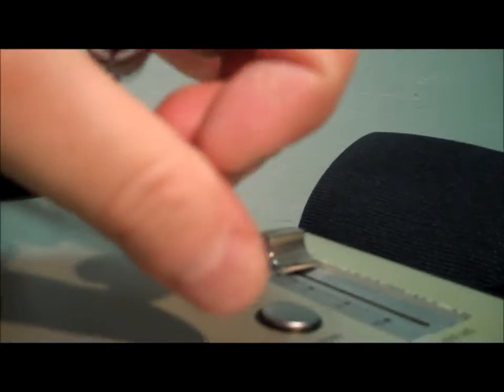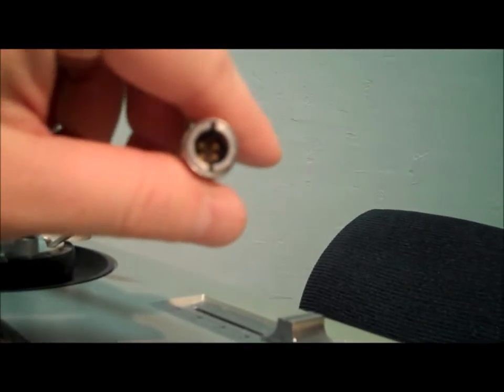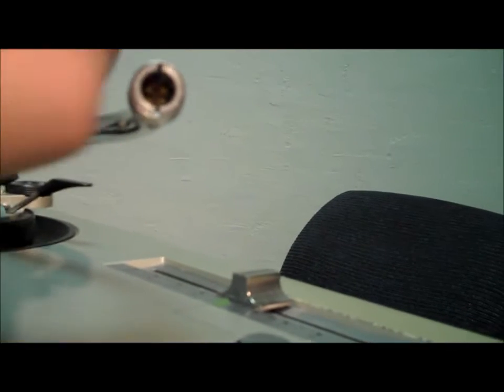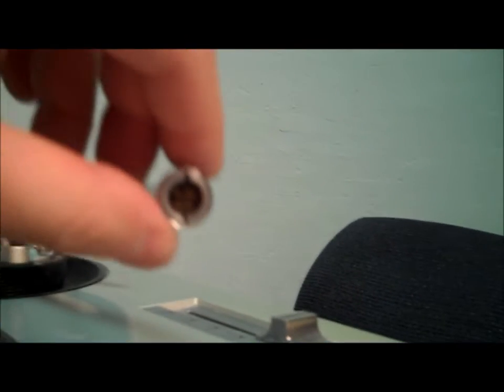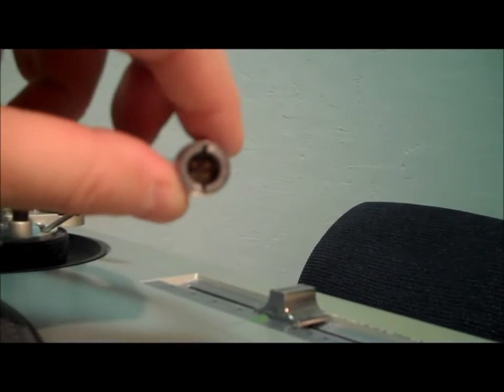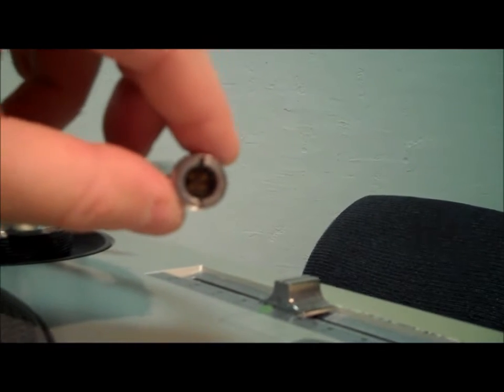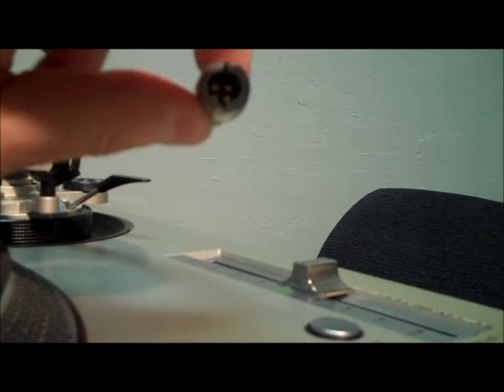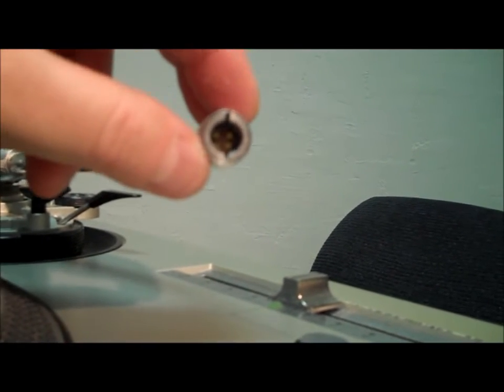And so you might want to take some napkins and wrap them around the head of this thing, and then take the tube. There's usually a little plastic straw that goes right onto the cap and onto the spray head here, and you spray a really quick squirt into there. And then take a Q-tip and swab the excess out. A lot of times that helps you clean the rust off of the prongs. So that's one way to troubleshoot it.